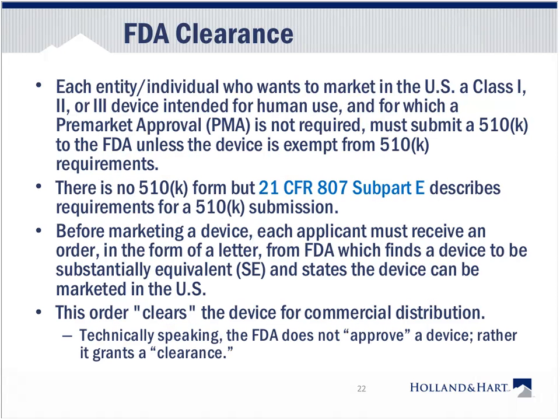Each entity or individual who wants to market in the U.S. a Class 1, a Class 2, or a Class 3 device intended for human use, and for which a pre-market approval is not required, must submit a 510K to the FDA unless the device is exempt from 510K requirements. That's a mouthful, and that's right out of the code. But I just want to say it one more time. If you are going to market either a 1, 2, or 3 device intended for human use that does not require PMA, so pre-market approval, you must submit a 510K unless the device is exempt.